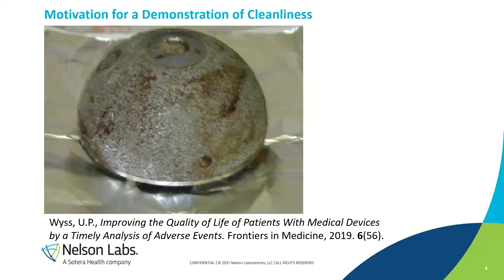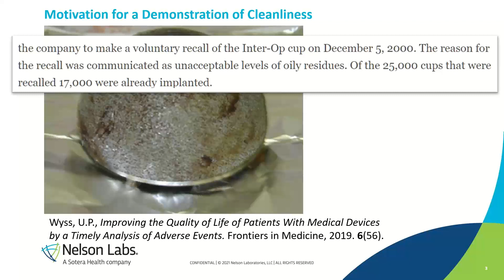So before we get into validation development, I wanted to just give a quick history check that many of you are probably already familiar with, but just in case. One of the more famous cases which illustrated the gap cleaning validations would cover was a situation with orthopedic implantable devices. So during the manufacture of acetabular cups, oil was actually introduced to the device. And I don't know if the oil was not noticed or if it was just deemed a low risk because at the time the biocompatibility had actually met requirements for that time. But these high residue devices were implanted into thousands of patients. And unfortunately, residue prevented successful osseointegration and caused inflammatory reactions, which then led to thousands and thousands of recalls.